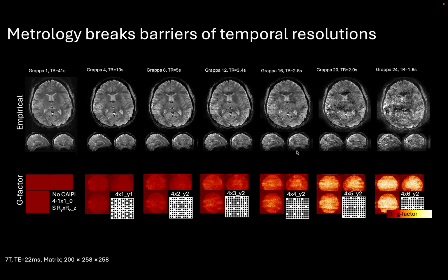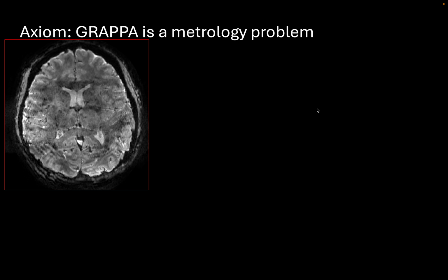If you look at the reconstruction literature, they would tell us, yeah, the limit of GRAPPA is the g-factor. This does not look like g-factor to me in practice, right? The g-factor would be salt-and-pepper noise amplification, random noise, right? However, when you look at this very carefully, we are not SNR limited. No, we are artifact limited. We have all these EPI issues there. It's just that GRAPPA is very sensitive to these artifacts, and it's actually amplifying any miscalibration of your scanner.